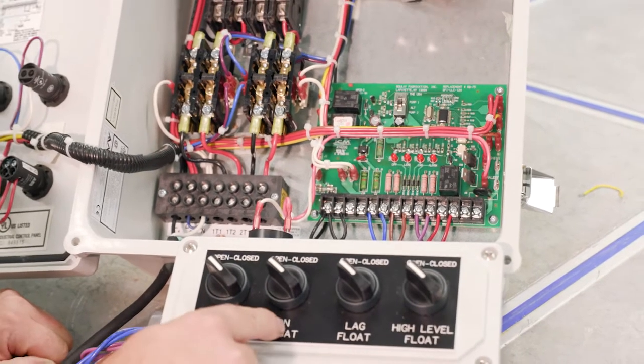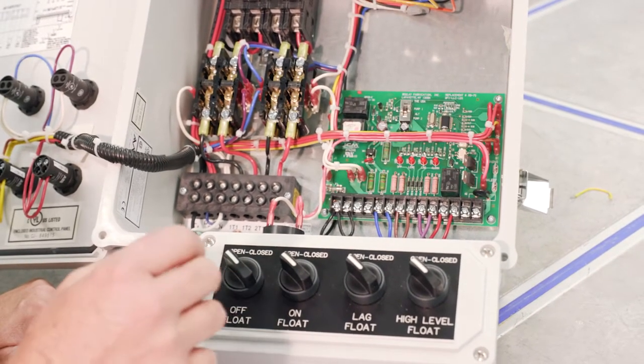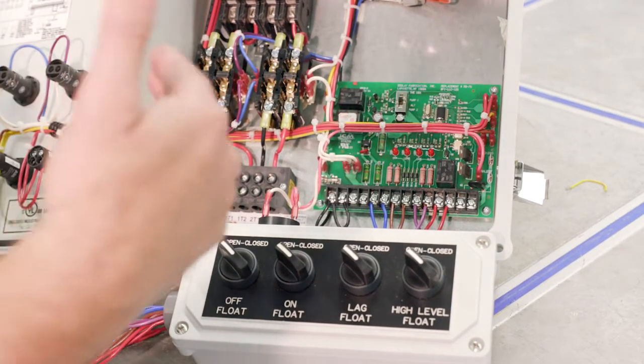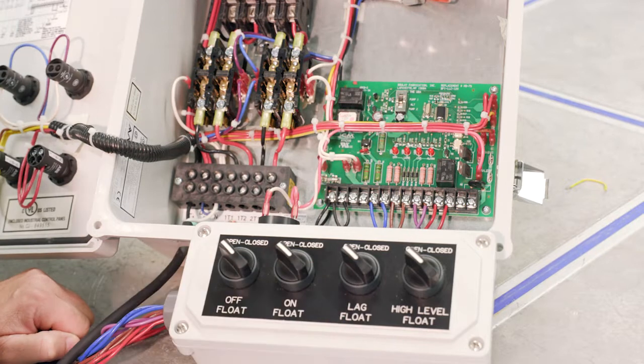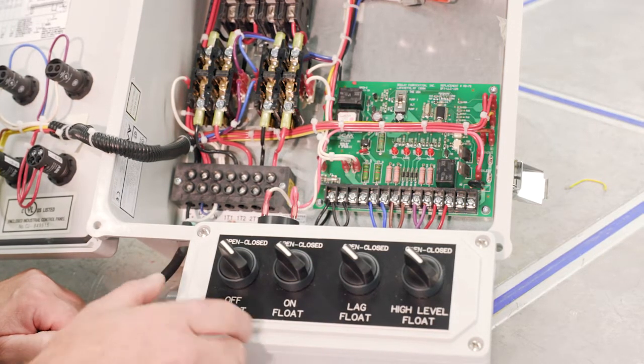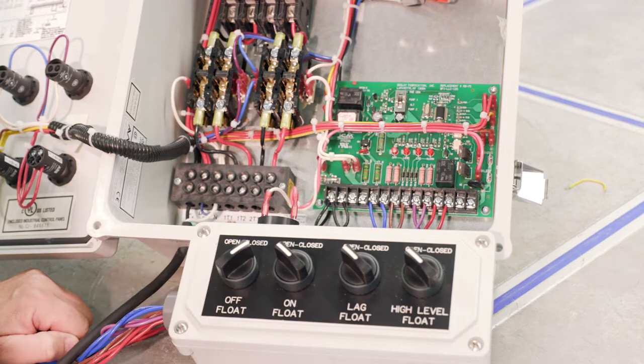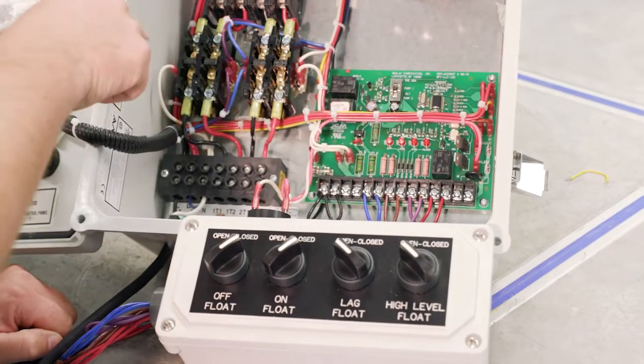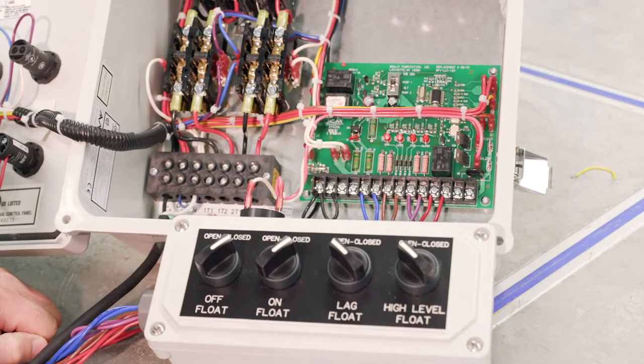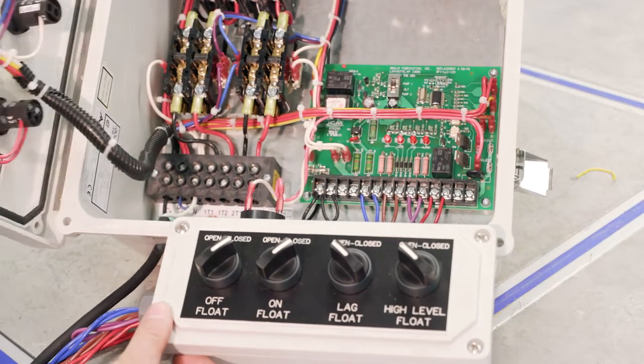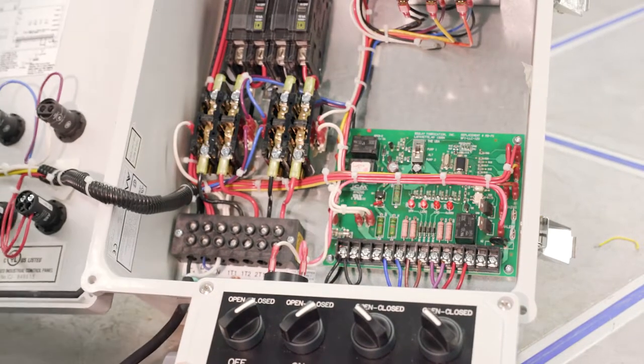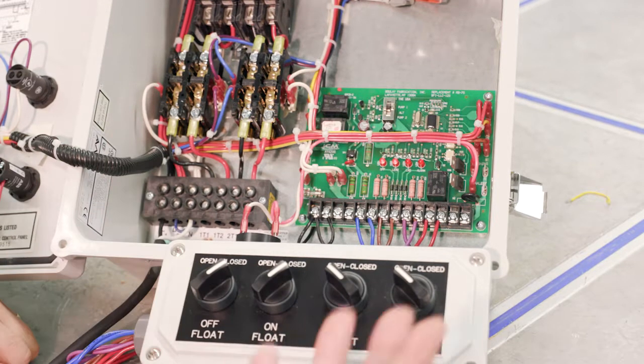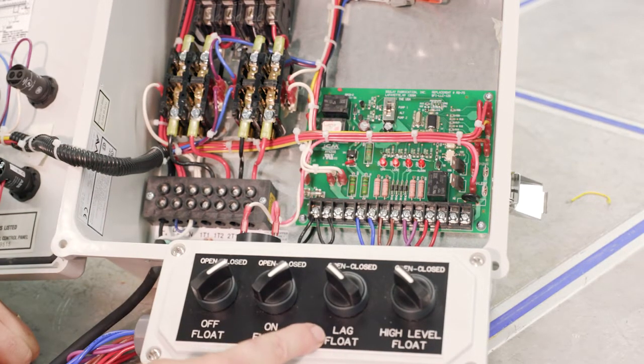So the next scenario is, let's say that the on float does not keep up with the demand. Water level is still rising, it gets to the lag float. So we'll go through that scenario. Off float, just the light, nothing else. It's on float, the light alternates now. So just to see which one is on, pump two is on. But again, let's say that doesn't keep up. Water level is rising, it gets to the lag float.